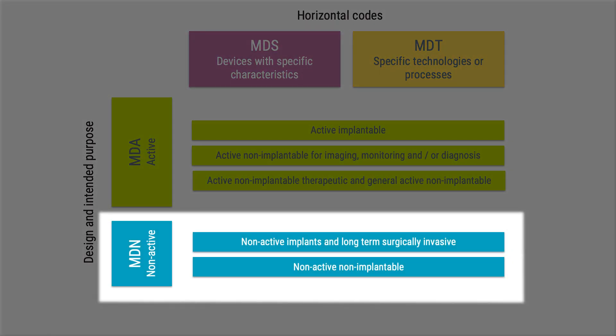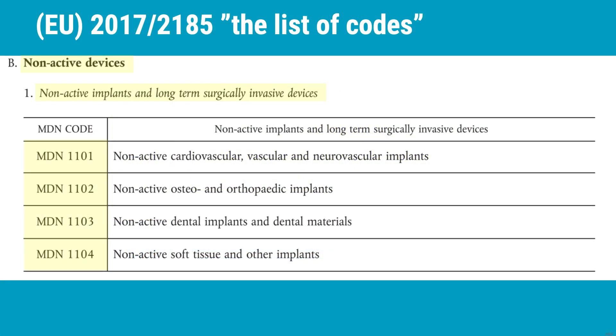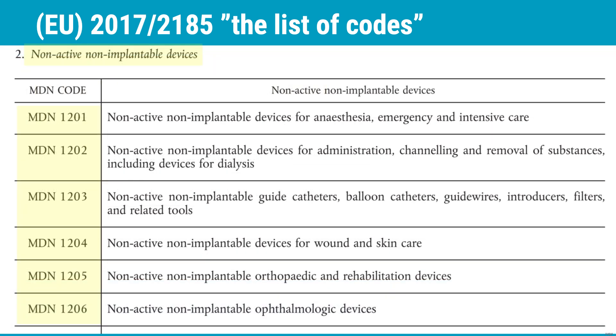Turning to the non-active codes, the MDN, with its two subgroups. The MDN codes start with the group for non-active implants and long-term surgical invasive devices, with four different categories of implants. The other MDN group is non-active non-implantable devices, which has 14 categories in it — here you only see the first six. This is basically where you find the rest of all devices. That was the MDA and the MDN codes.